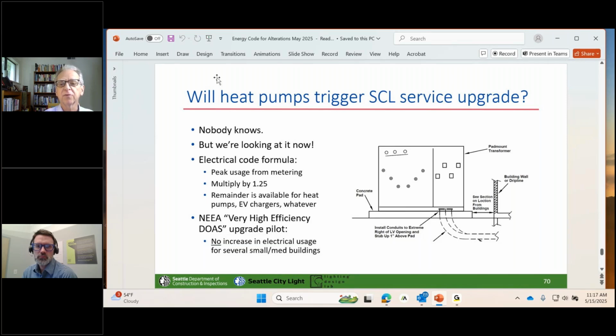Another thing to note is a project that's been going on at NEEA, Northwest Energy Efficiency Alliance, for the last several years—what they call a very high efficiency DOAS upgrade—where they've taken a number of typically low-rise buildings and switched their system over to a DOAS system. They found that not only did they eliminate all fossil fuel usage for those spaces, but they did not increase their electrical use at all. The reason being that traditional systems have been incredibly inefficient—fan energy, reheat energy, many other things engineers have traditionally been doing for generations—so once you've gone to an efficient system, you might find you didn't need to upgrade at all.